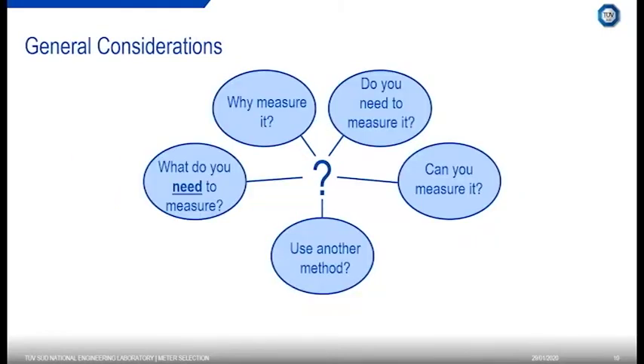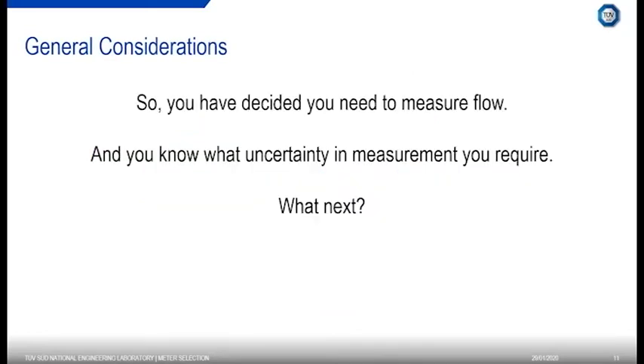Each meter has its own advantages and disadvantages. There are general considerations when specifying a flow meter. First: why are you measuring it? Do you need to measure it? Can it be measured — is it an extremely corrosive fluid, or at extreme temperature or pressure? Could you use another method — is it a batch process where you could just weigh the product at the end? What do you need to measure, and why — is it for fiscal measurement or a legal requirement? Once you've established that you do need to measure it, and you know the required uncertainty, you can move to the next step.